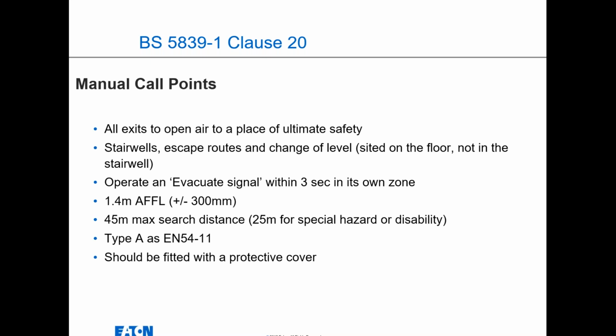Ironically, in 2013, I think it was a variation if you put a cover on a call point, because it was a double action. You had to lift the cover to press the call point. Nowadays, in the 17 version, it's a variation if you don't have a cover. All of ours come with the option of plastic covers, and it helps to minimize false alarms from people just being the devilment factor of breaking a call point, whether that's in a school or not. And obviously, if it's a real problem, you can get ones with sounders on them. So if you lift it, a siren goes off, so it is even more of a deterrent than a standard plastic cover.